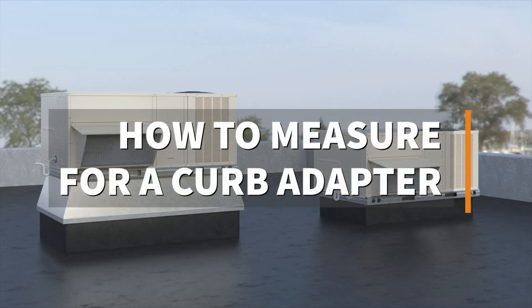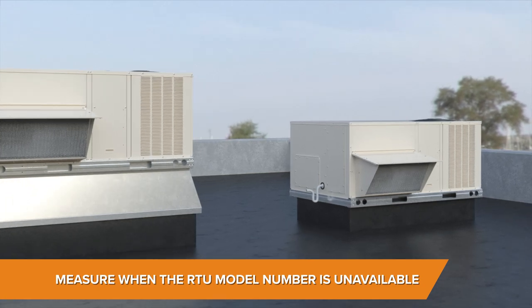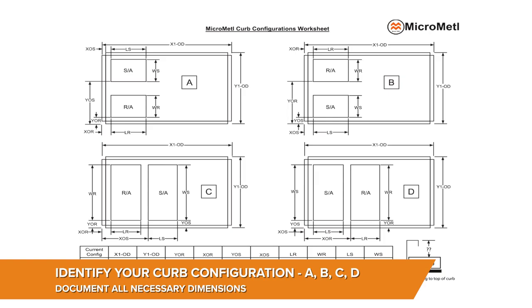How to best measure for a curb adapter. What do you do when you have no model number and you need to replace the RTU? Time to measure. MicroMetl offers a curb adapter worksheet that you can download from curbadapter.expert. This will allow you to collect as much detail as possible while on the rooftop.